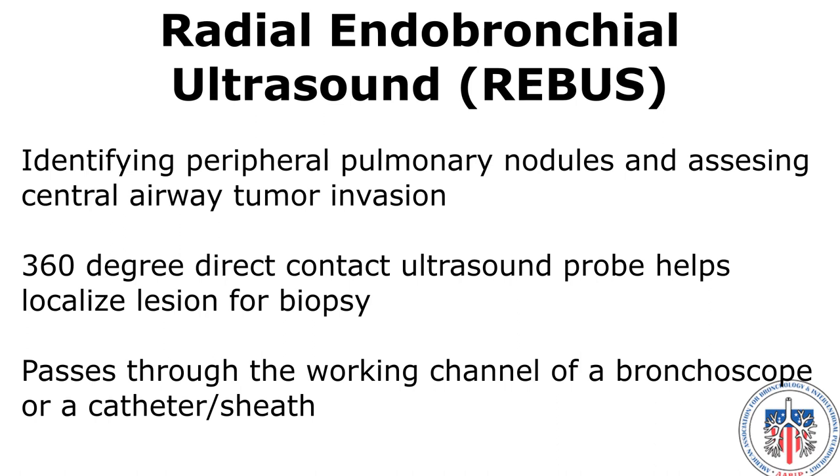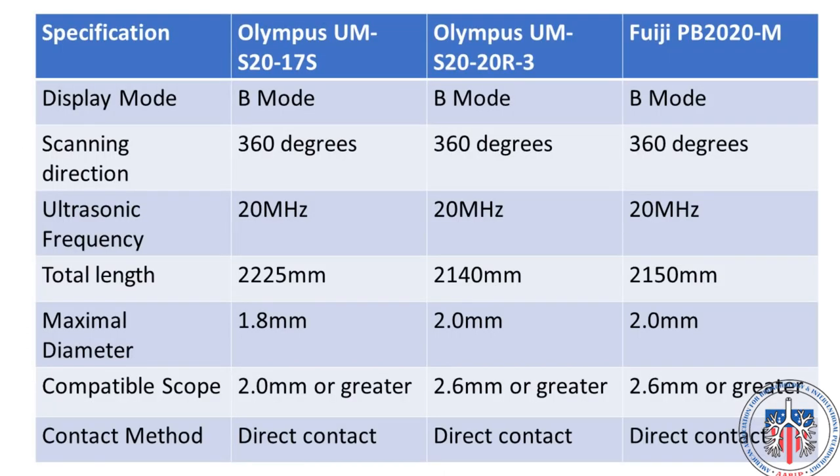The radial probe helps identify and localize lesions for biopsy with a 360-degree direct contact ultrasound probe that passes through the working channel of a bronchoscope. There are three different types of rEBUS probes available in the United States for peripheral pulmonary lesions — two made by Olympus and one by Fuji. The first probe, the Olympus UM-S20-17S, is the most common probe currently used because it is the smallest in size at 1.8 millimeters and fits through the working channel of a bronchoscope as small as 2 millimeters in diameter.